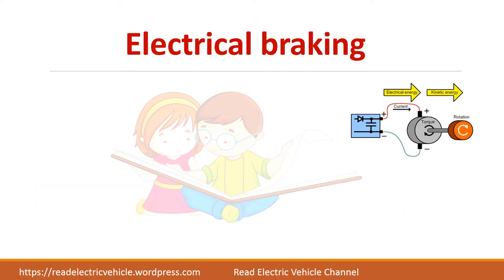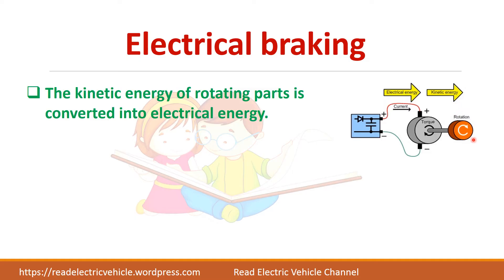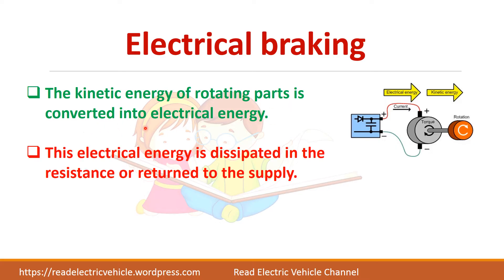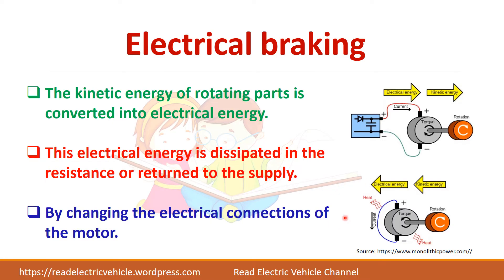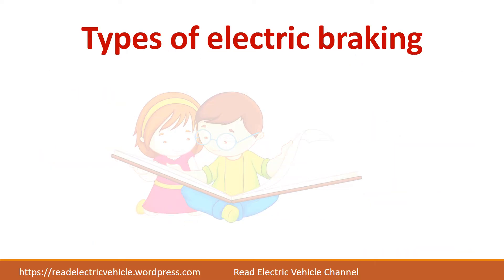When the motor rotates, the electrical energy is converted and stored in the rotating parts as kinetic energy. When we apply the electric brake, the kinetic energy of the rotating parts is converted back to electrical energy. This electrical energy is dissipated either in a resistance — so it becomes heat — or you can return this electrical energy to the supply. There are two options: either you dissipate it as heat, or you return it back to the supply. This is done by changing the electrical connections of the motor.